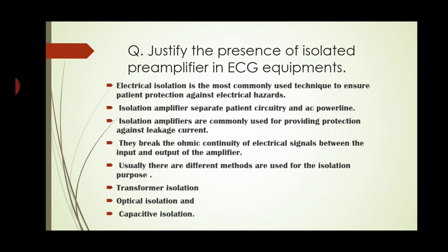Now we will see the isolated preamplifier equipment. What is the use of the isolated preamplifier? It gives isolation. Electrical isolation is the most commonly used technique to ensure patient protection against electrical hazards.